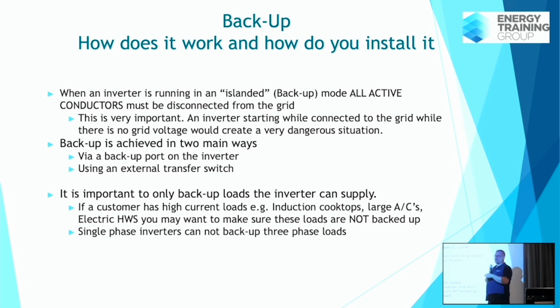So to go into an off-grid mode, it's really, really important that whatever you do, all active conductors are disconnected from the grid when you go into backup mode. Now, that's usually achieved in two ways with inverters. You'll either have a backup port on the inverter or an external transfer switch.